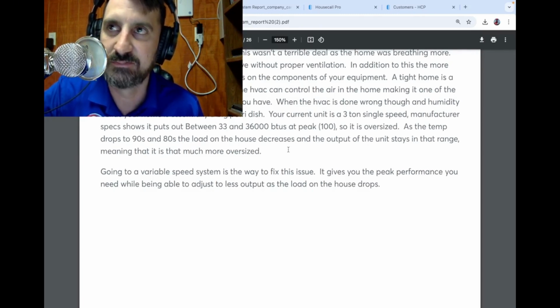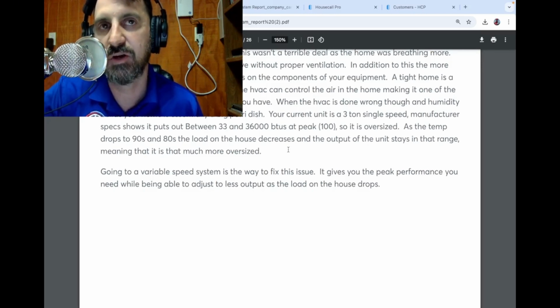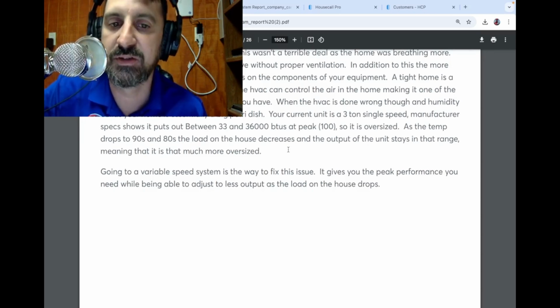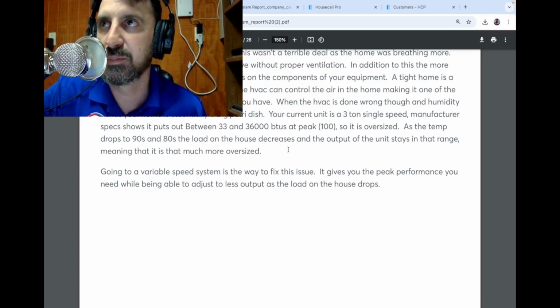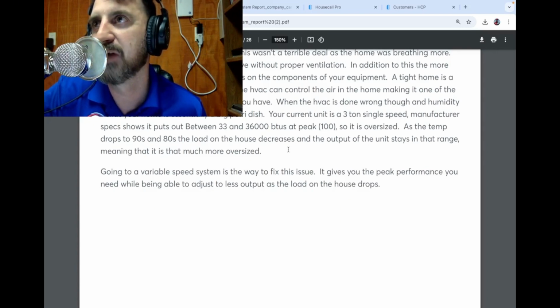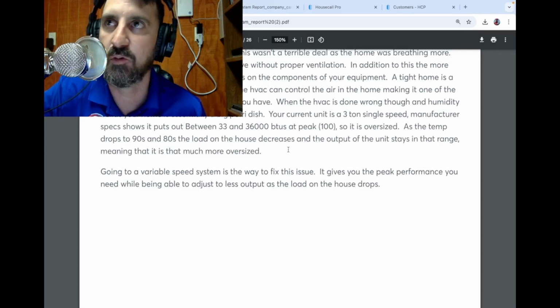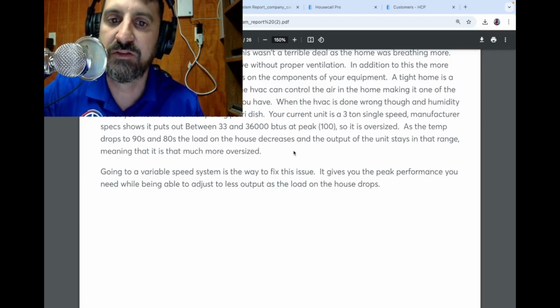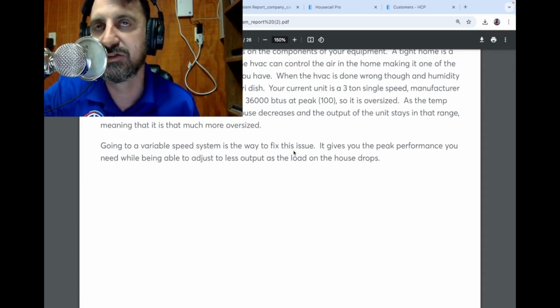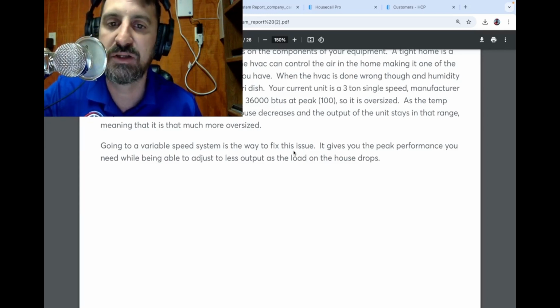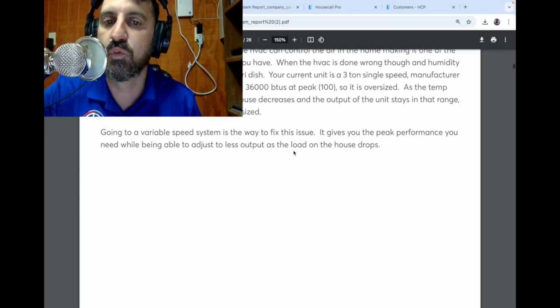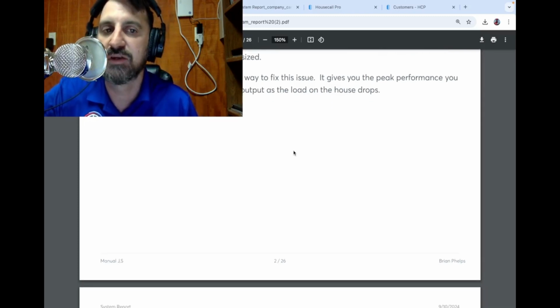If, however, you do not do all of those things and you have a tight home where you're not removing humidity properly, you're not bringing in fresh air properly, your house is essentially a petri dish. You go ahead and put some moisture and organic material of any sort into a petri dish and see what happens. But basically, that's the whole idea behind the manual JDNS: you want to know how many BTUs you need to cool the house. You want to know what systems are capable of doing that. And you want something that can vary within a range to keep it close to that.